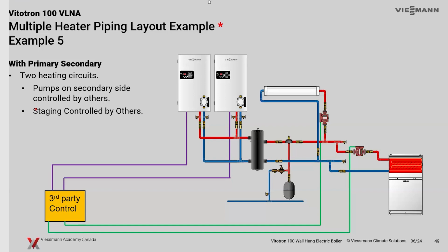So you're really only limited to the capacity of your incoming power as to how many of these electric boilers you can cascade into a system here, and of course the limits of the control you're using. But this would be typical system operation off of third-party control, and your boiler enable-disable off third-party control. And the boilers are essentially just going to operate their staging of their own individual elements based on their own individual logic. So the actual cascade control doesn't look after the individual staging inside of the boiler elements themselves. That's all looked after by the boiler. And of course, it's differential temperature from supply and return.